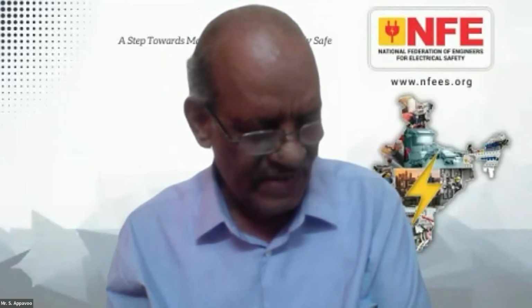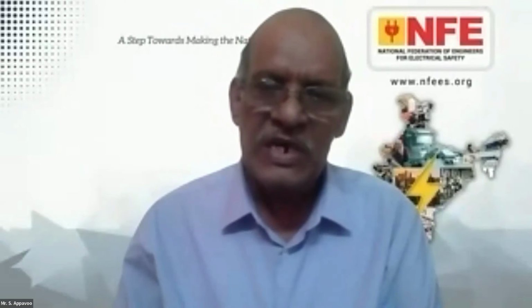You can see all the basic things of NEC code and the regulations are quoted therein. One important thing I can say is, with regard to earth leakage and other things, the residual current, here also they have furnished one stipulation that RCD should be monitored and provided. So what I suggest is, there could be some DC, smooth residual DC components also. What type of RCD you have to provide is more important.